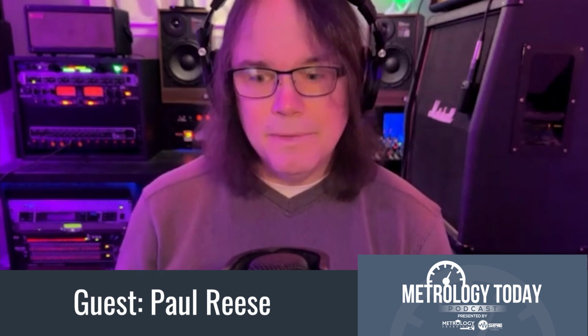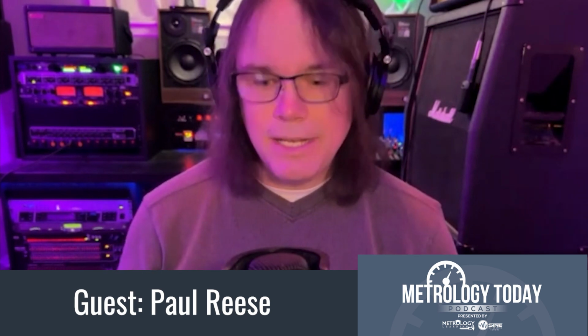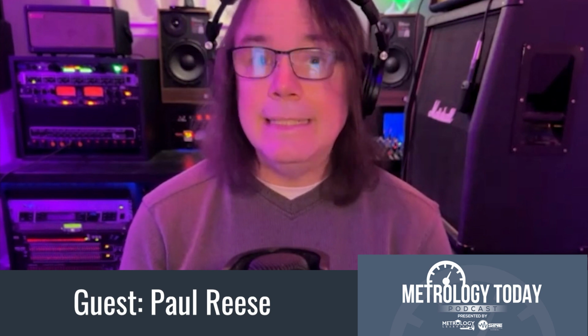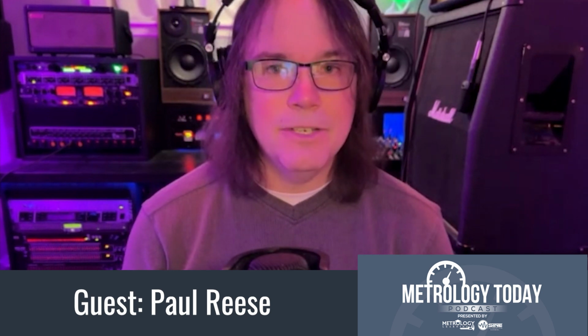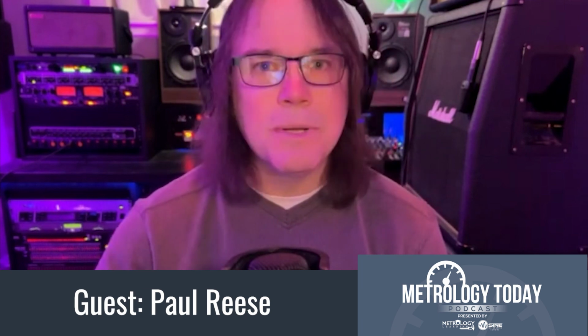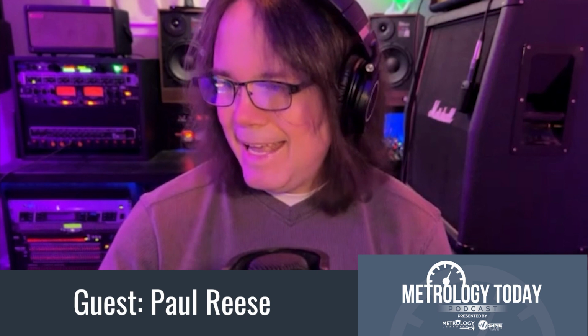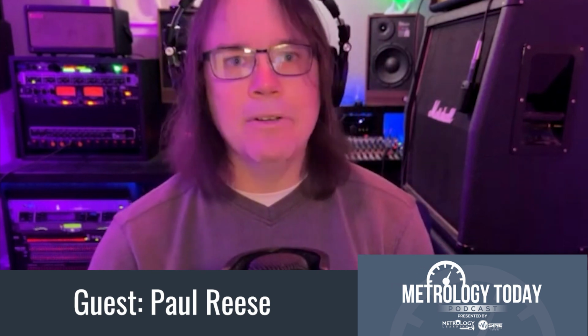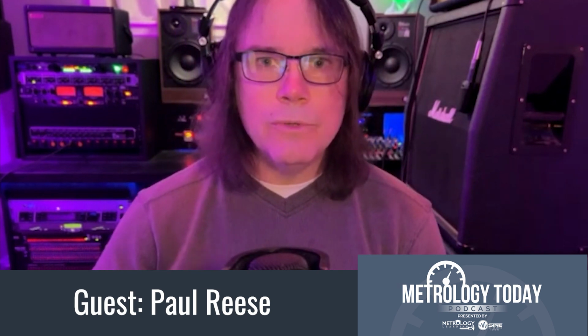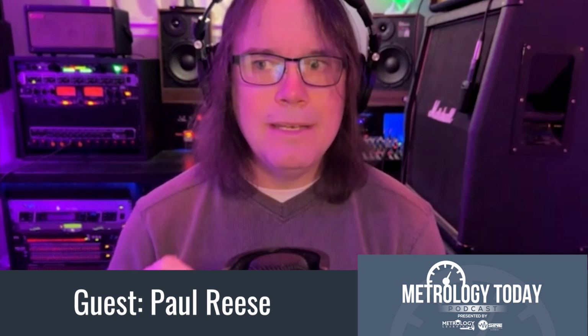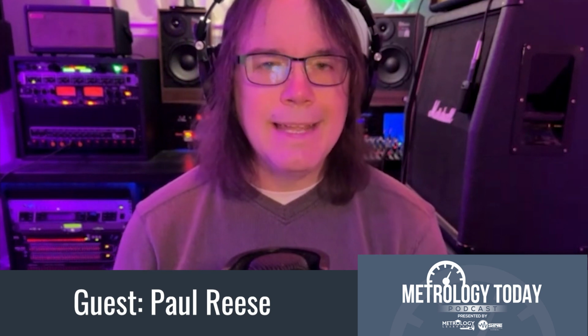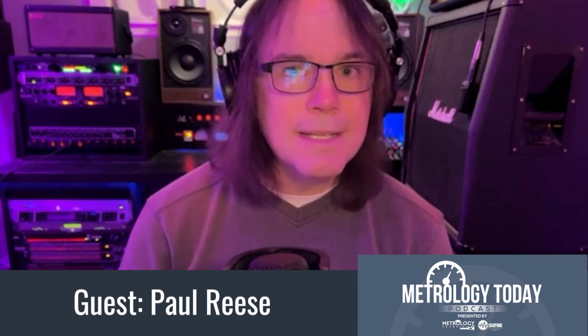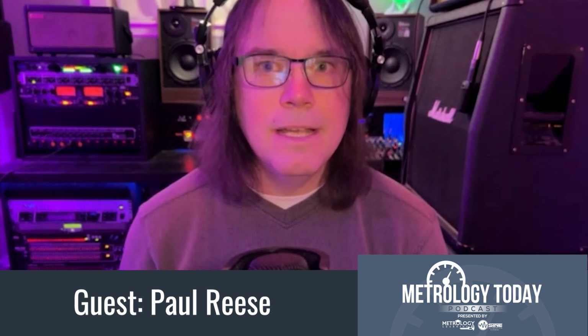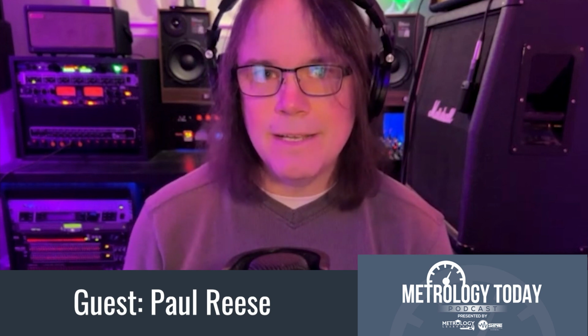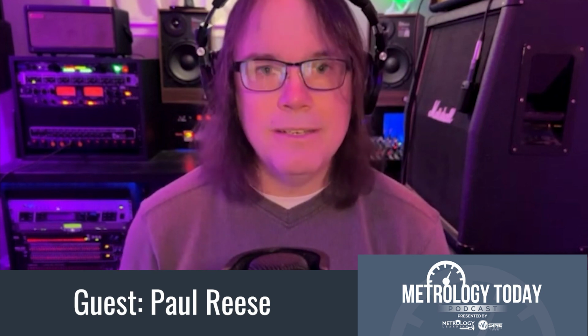Technician B comes up, looks at the same micrometer. Nothing's changed. The micrometer's still placed on the gauge block. Nothing has changed. And technician B writes down a number and says, this is what I think this micrometer reads. And it's close, but it's barely out of tolerance. So two technicians have written down two different numbers and came to two different conclusions. One says in tolerance, one says out of tolerance. So there is measurement decision risk here. We cannot make a confident decision.